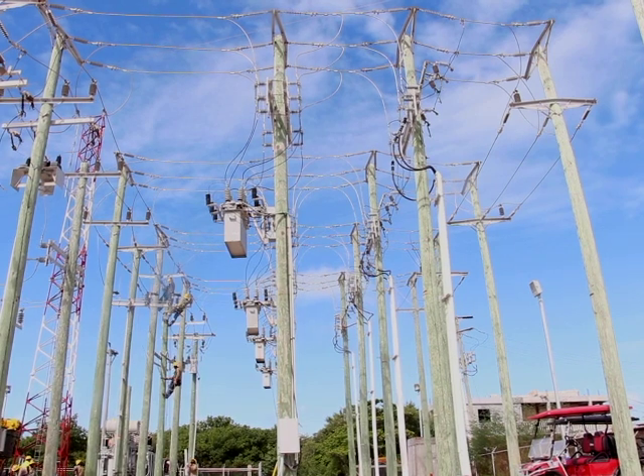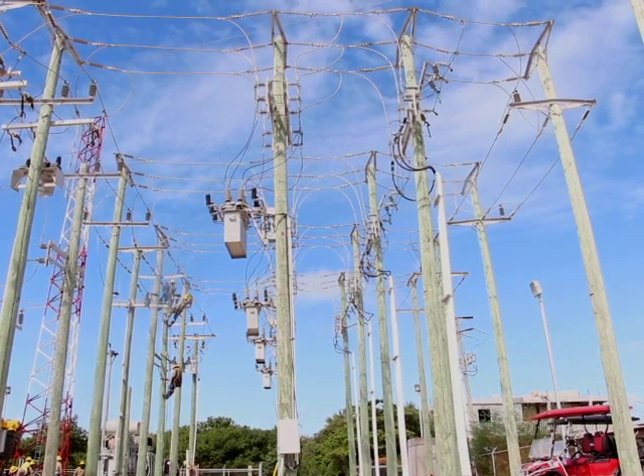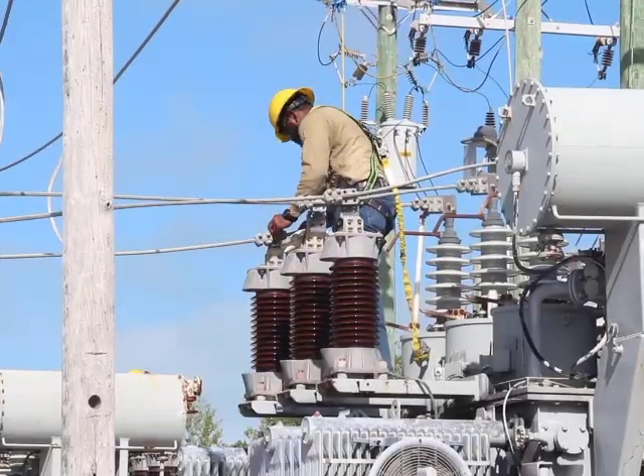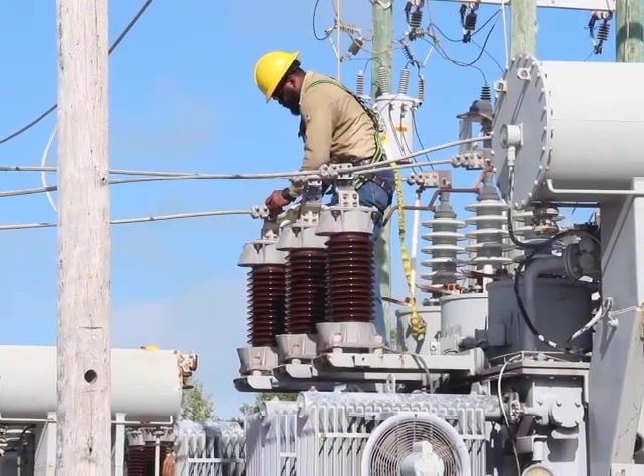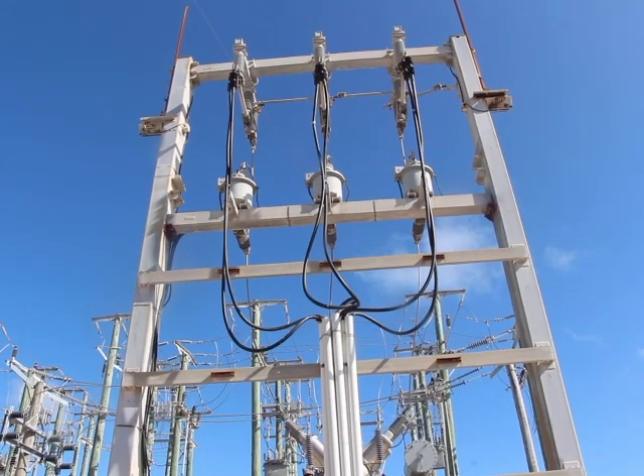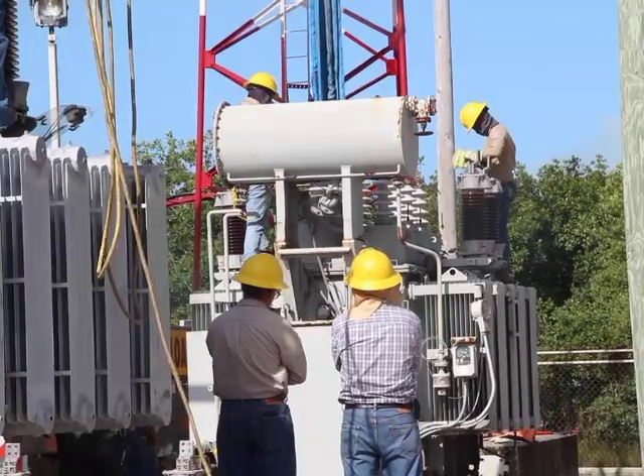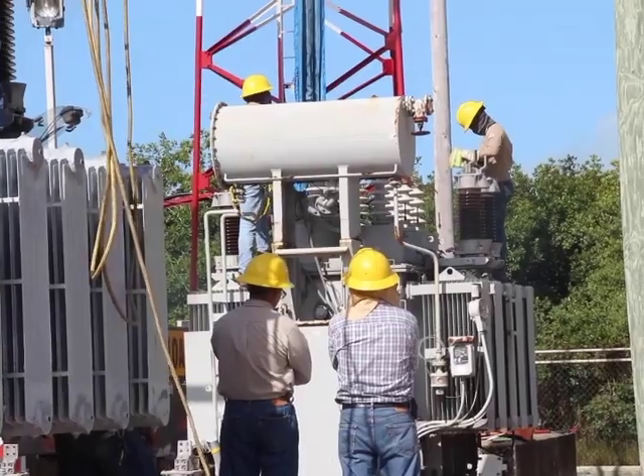Today's job was to relocate a transformer, and at the same time we took advantage to do preventative maintenance. That's what we did with the next transformer, because we have two transformers. For the next one, we basically just test arresters, and if they give a bad reading, we take advantage of the situation and replace them, because those are very critical. If they fail, then the transformer fails, and then you have an outage.